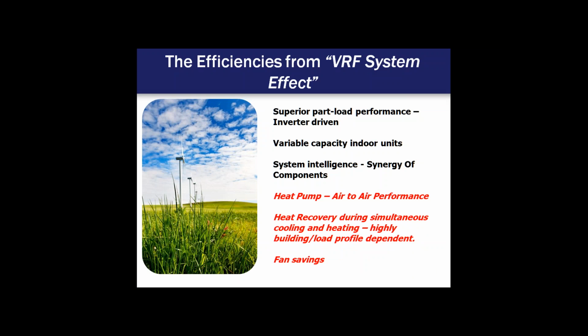Again, looking at the efficiency effects from the VRF system, the superior part load performance is attributed in large part to the inverter-driven scroll compressor, the variable speed compressor, the variable capacity indoor unit control, and the smart coil technology. Each of those units has a linear expansion valve precisely throttling the refrigerant at any given time. And then the system intelligence, that packaged DDC control, allows all those units to operate, both day one and throughout the life of the equipment, at their most efficient, optimal level.